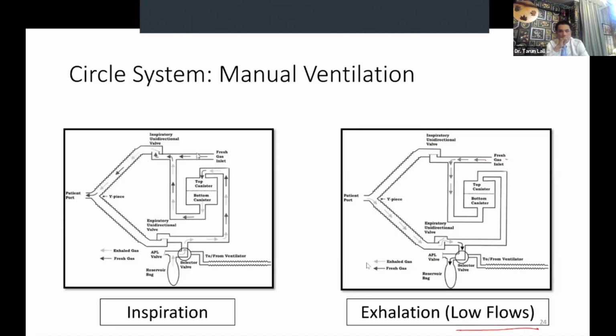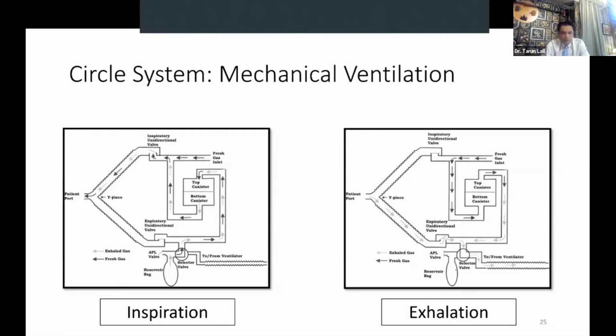If it is low flow, it reaches only till here. If the flows are very high, then some amount of fresh gas flow, because you see that it is a valveless system, will reach the bag, and so the bag will contain some amount of fresh gas also. At low flows, the bag will contain mainly exhaled gases. What happens during mechanical ventilation? Now, in mechanical ventilation, you'll see that the bag selector switch is now towards the ventilator. So the bag is now out, and the gases flow in a similar manner.